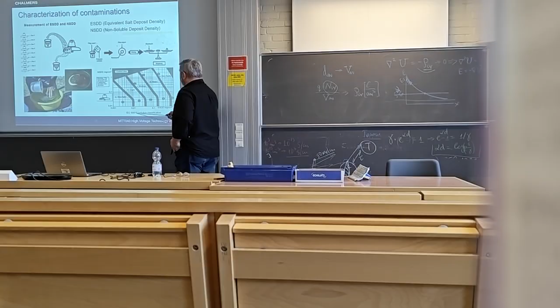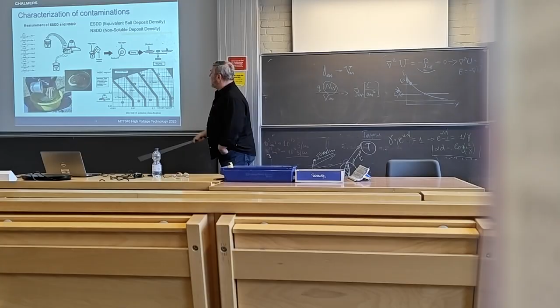This is taken from the standard. There is a relation between the ESDD values, milligram per square centimeter, and NSDD values, milligram per square centimeter. So there is some kind of equivalence one can think about, and depending on the level, it's classified: very light pollution below this line, then light, medium, heavy, very heavy. That's how the standard classifies these things. Of course, if you go to the right, it's much more dangerous for the insulation.